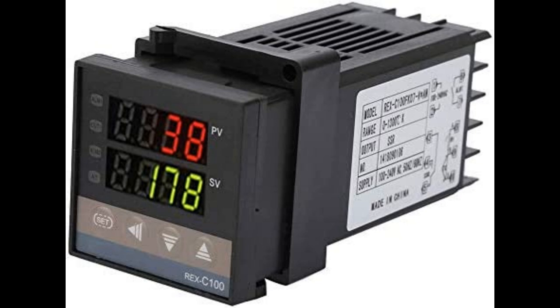A safety critical point to note here is that the still is designed to be operated continuously unattended and it must therefore fail safe. Inexpensive commercial thermostatic and PID temperature controllers switch heaters using relays and relay contacts have a limited life, particularly when switching high powers because switching causes arcing at the relay contacts which slowly degrades their coating. Ultimately, this leads the contacts to weld together after typically 50,000 operations.